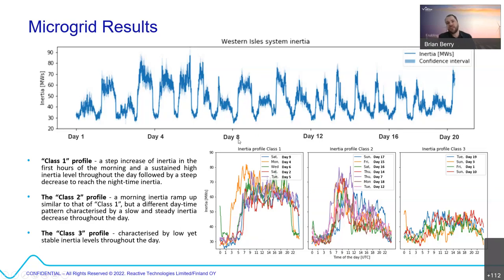Now, what's interesting about this is, you look at the demand curve and you say, okay, this is simple, I've seen this before. You're going to have a certain pattern on the weekday, a certain pattern on the weekend, a certain pattern in summer, a certain pattern in winter, and it's all going to make a lot of sense. But when we looked at this data, we were able to classify three different profiles. The first one has inertia stepping up in the morning, staying up the whole day, and dropping off in the evening. That's pretty common. That's what I would expect a weekday to look like.